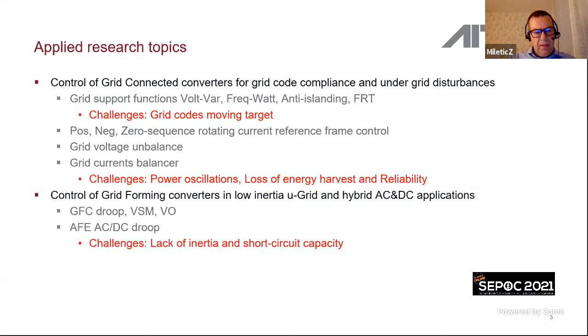Next topic that we cover in our applied research is grid forming converters in low inertia microgrid and hybrid AC-DC applications. As far as GFC, our grid forming converters, we are focusing on droop, VSM, matching control, and virtual oscillators. And in AC-DC hybrid applications, on active front end with DC droop. The biggest challenge in microgrid applications with low inertia and hybrid AC-DC applications that we see at the moment are lack of inertia and lack of short circuit capacity of these grids.